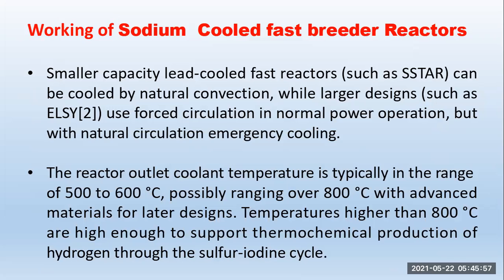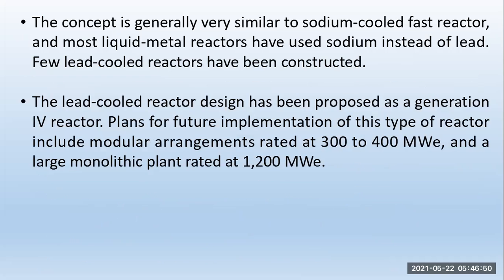Working of the sodium-cooled fast reactor: small capacity lead-cooled fast reactors can be cooled by natural convection, while larger designs use forced circulation in normal power operation but with natural circulation for emergency cooling. The reactor outlet coolant temperature is typically in the range of 500 to 600 degrees Celsius, possibly ranging over 800 degrees Celsius with advanced materials for later designs. The concept is generally very similar to sodium-cooled fast reactors, and most liquid metal reactors have used sodium instead of lead.